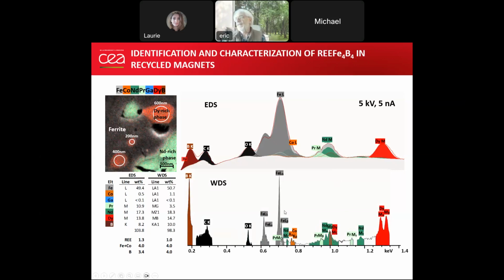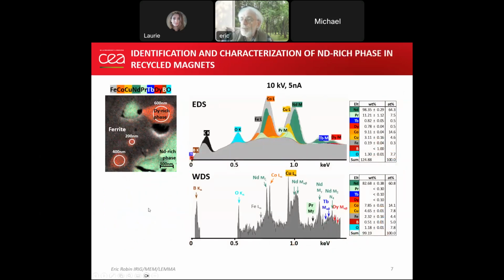So with this detector, with this spectrometer, it's possible to do this kind of analysis by reducing both the voltage and working at relatively low beam current. And the last example, of course, as I said at the beginning, is that it's necessary to identify all the phases. So this is an analysis of the neodymium-rich phase in green here. It's quite a large phase, so we can use a higher voltage of 10 kilovolt here.